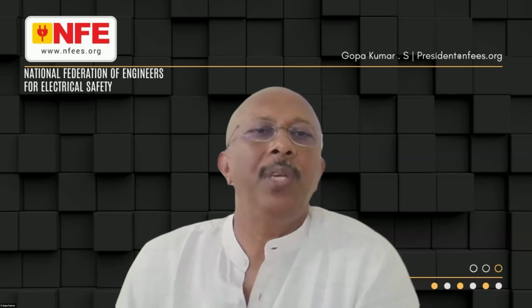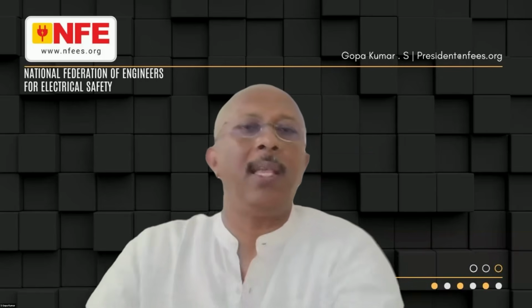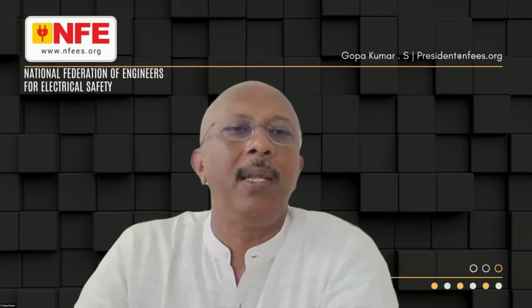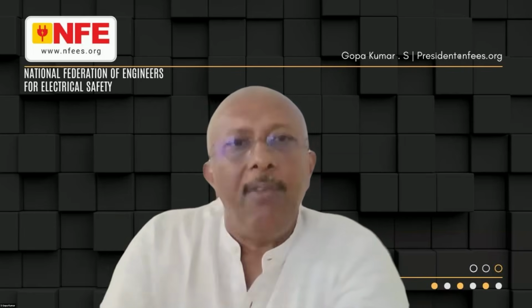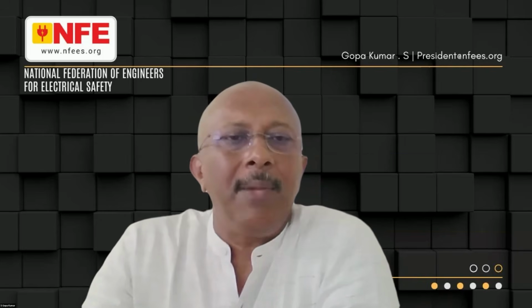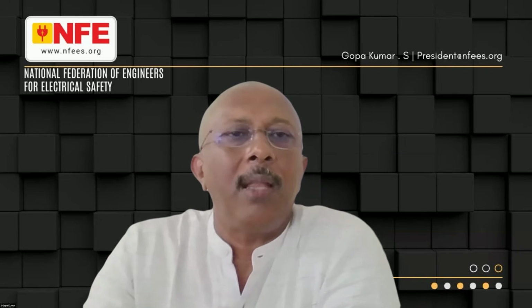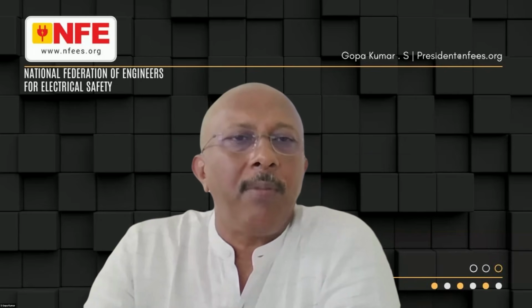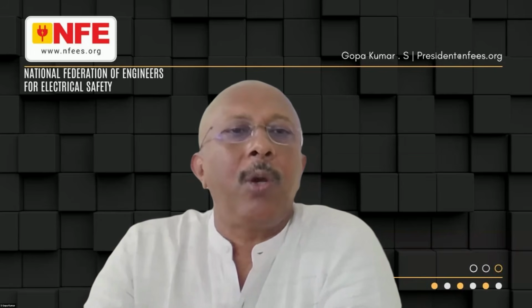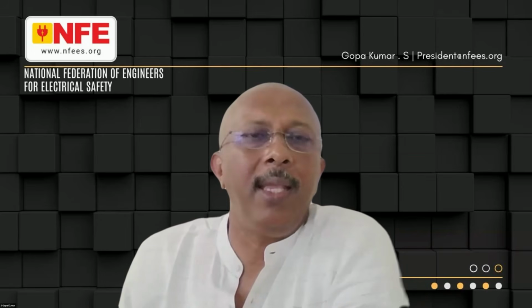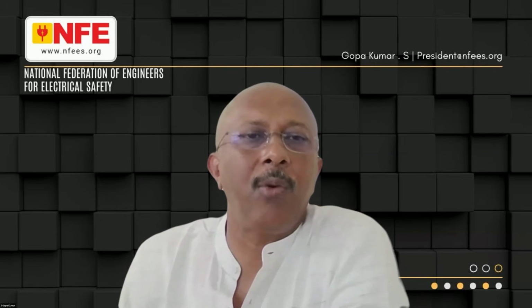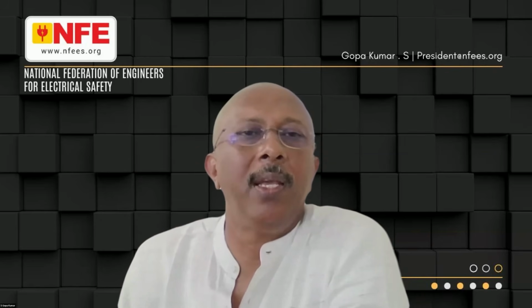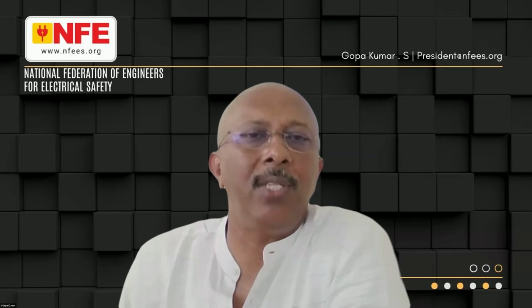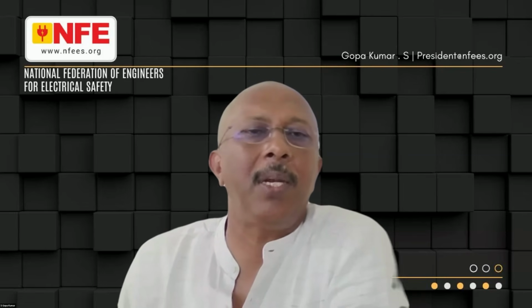Now, Mr. Jayvant Kumar Bolia asks: please explain the material, length and thickness of the earthing electrode for connecting the equipotential bonding plate to the ground. Mr. Bolia, if you are asking about the conductor sizing, the maximum conductor size from the common bus bar to the earth electrode is 25 square millimeters copper. If you are talking about the earth electrode, then you have to look into the table in IS 3043, IS 732, the National Electrical Code of India and the National Building Code of India, depending upon the different materials. Aluminum cannot be used as earth electrode. Copper, stainless steel, or copper bonded steel, in different sizes, are recommended in the standard.